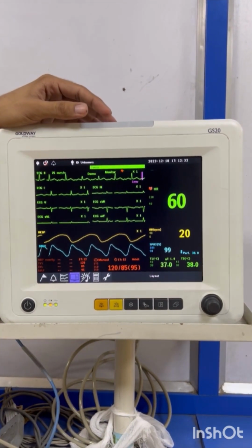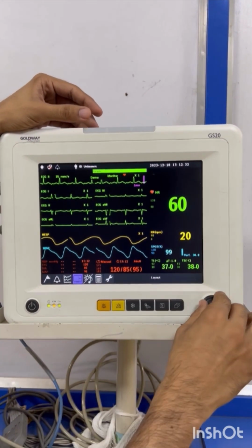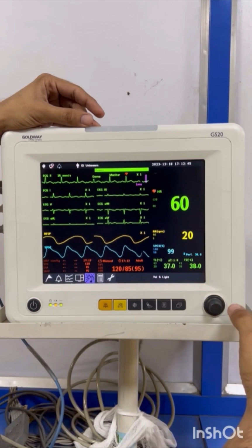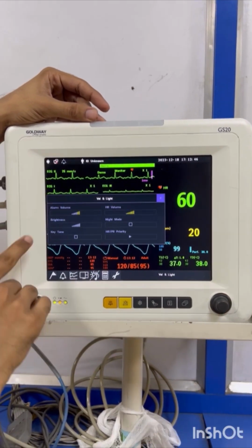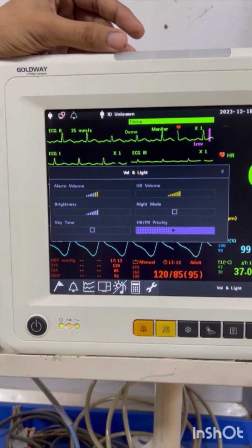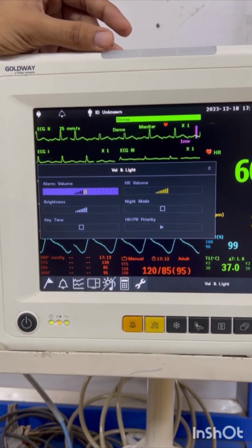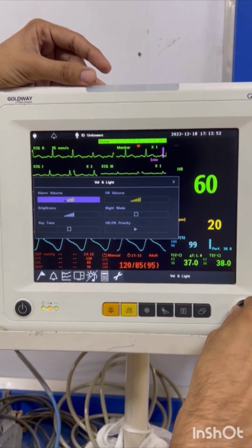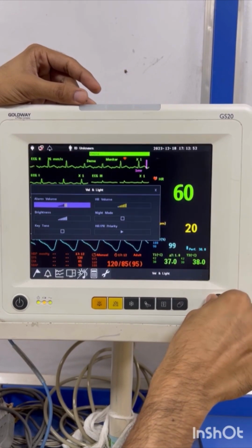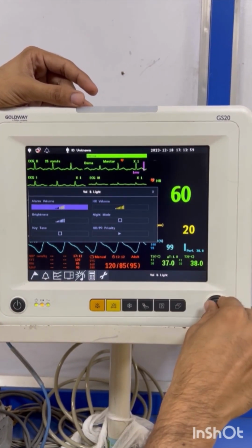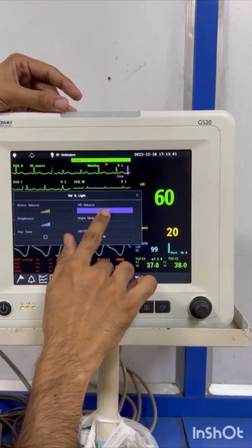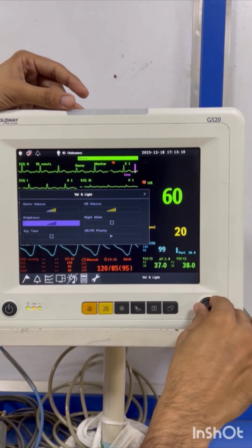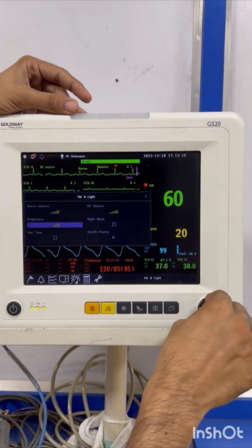How to set alarm volume and brightness in patient monitor. So we'll go in this parameter. We just have to select. We can change alarm volume. I'll go to alarm volume. I'll select from rotary knob, and I can just rotate the knob to increase or decrease alarm volume in patient monitor. Then this is for HR volume. This is the brightness. I can reduce or increase the brightness also.